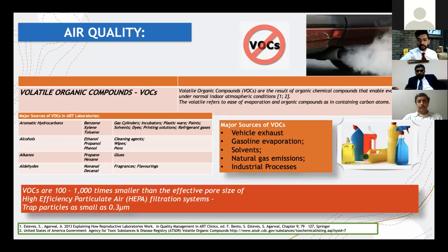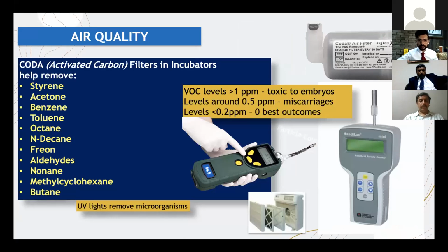As per the Cairo consensus, the VOC threshold level in the lab is around 400 to 800 ppb. Most labs in India use ppm-based photoionizers, but the lowest detection level is often limited to 1 ppm, which is equivalent to 1000 ppb. Many labs have a backlight indicator like green, orange, or red, so this needs attention. Some Indian companies offer quality control packages with PPB-based meters that people can use.